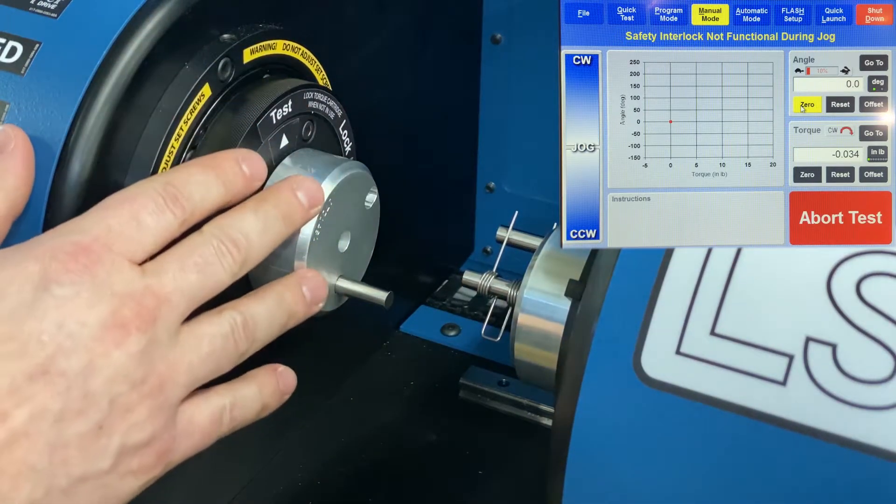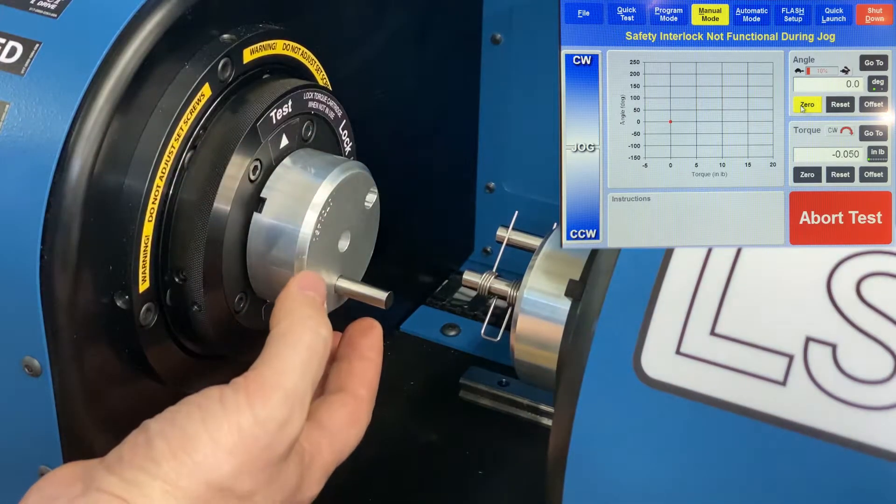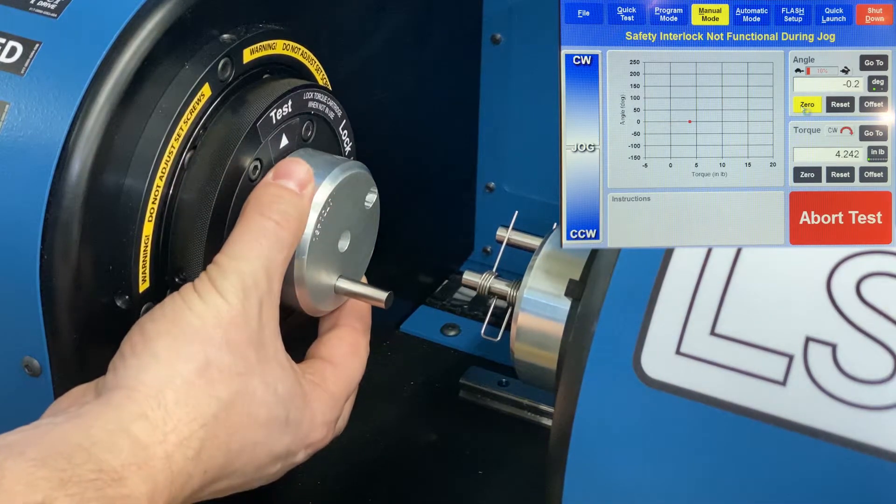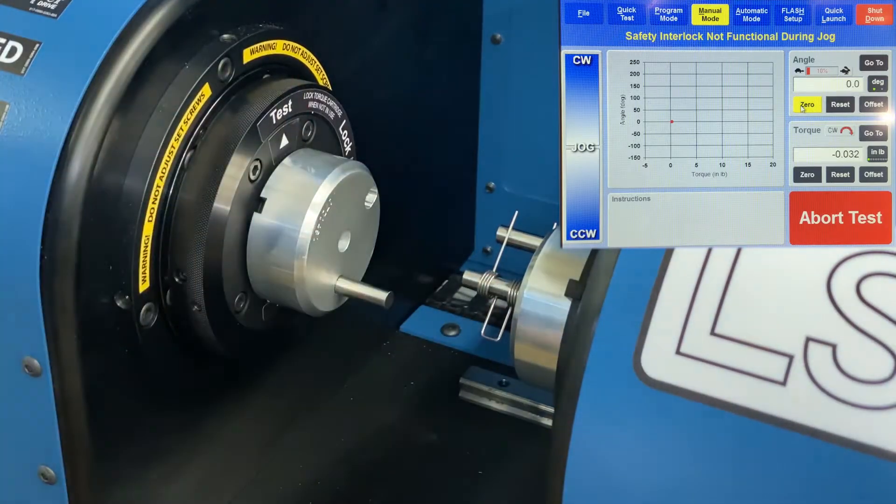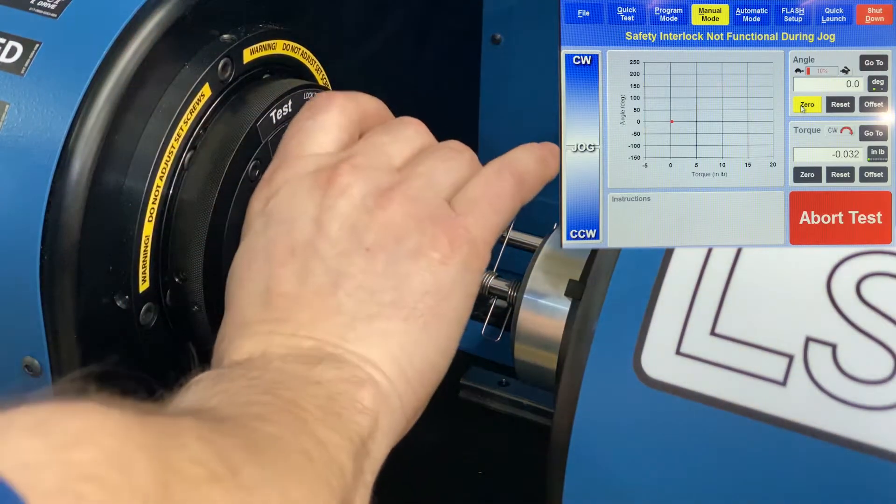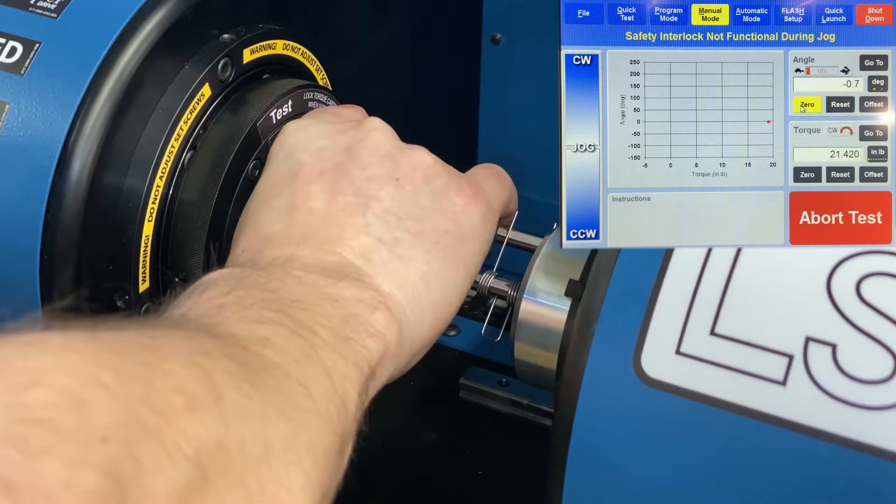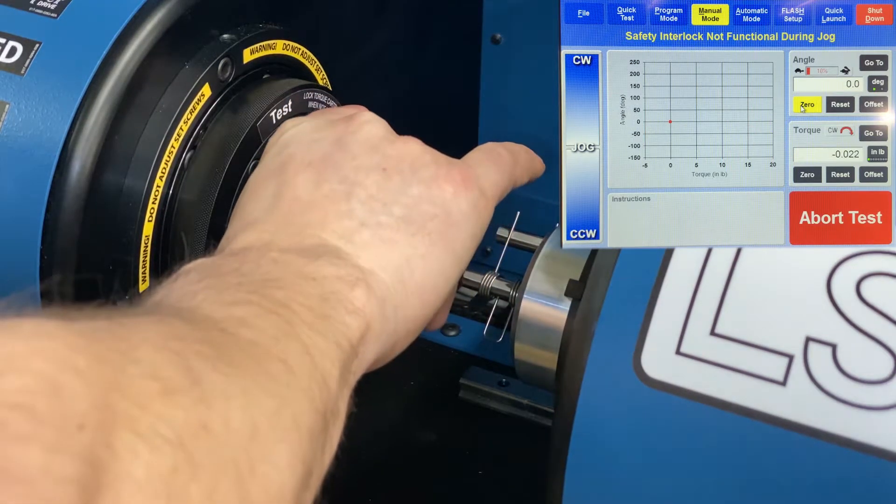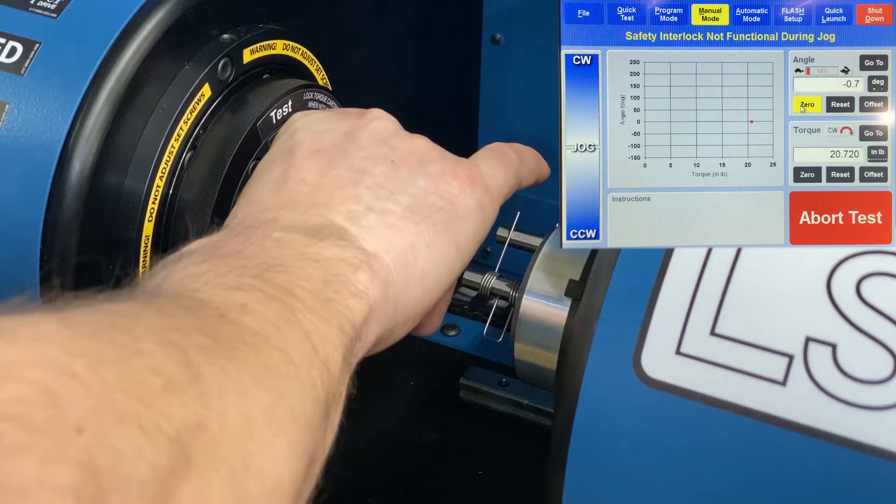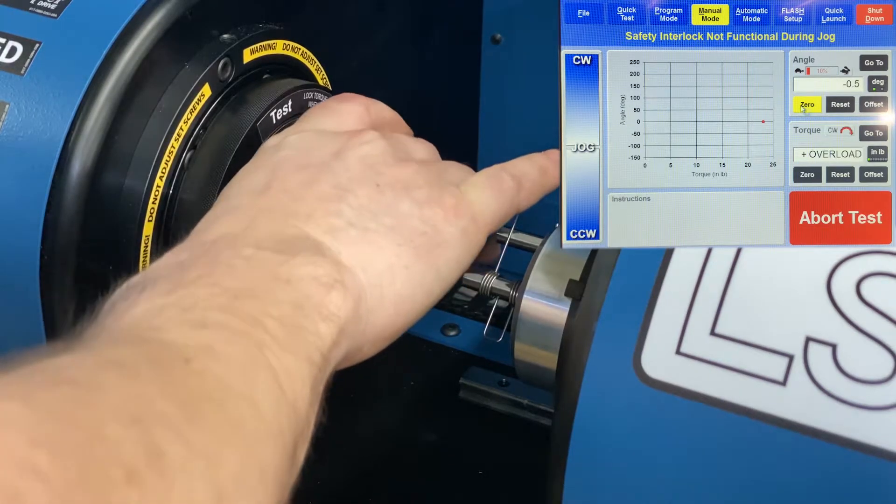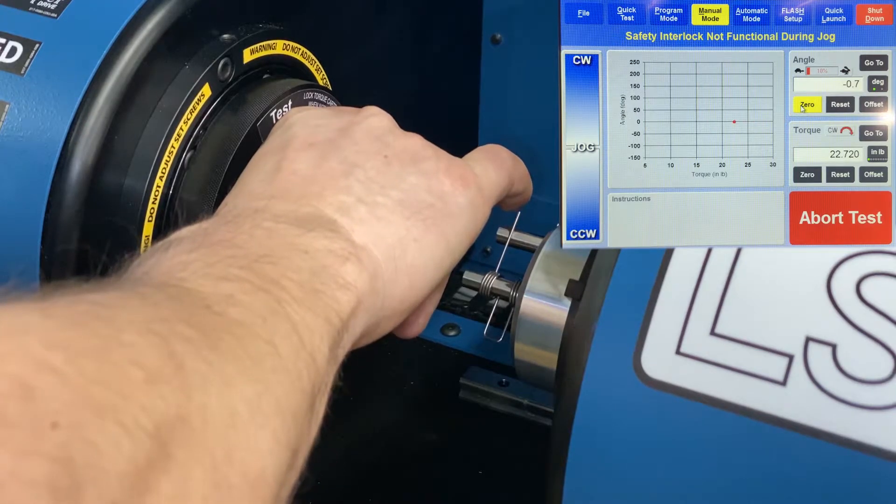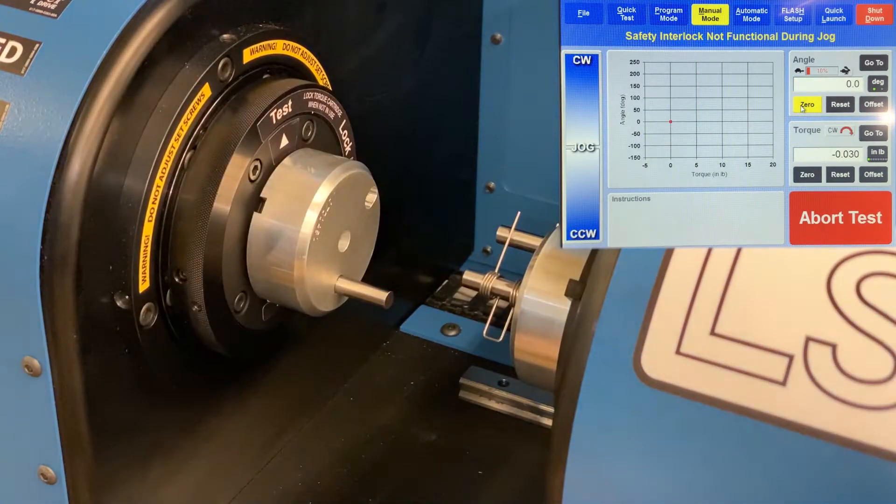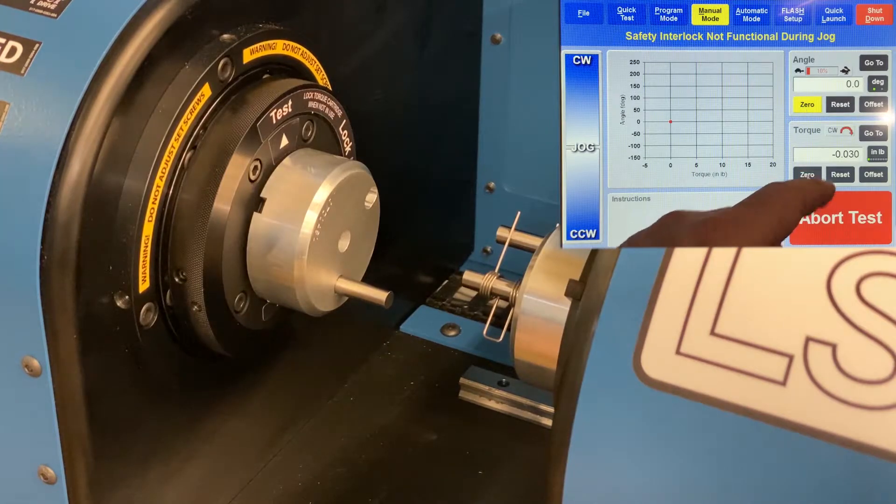Because this is only a 25 inch pound torque cell, I can actually manually exercise this using my hands, getting to 25 inch pounds three times to exercise that. One, two, three. And once it's done that, I can zero my torque.